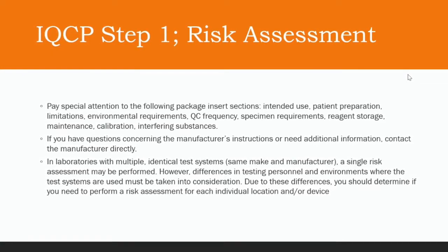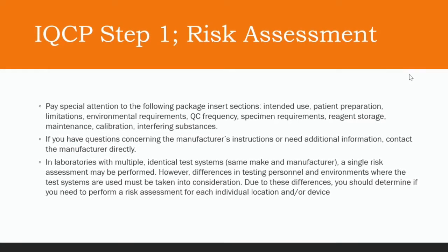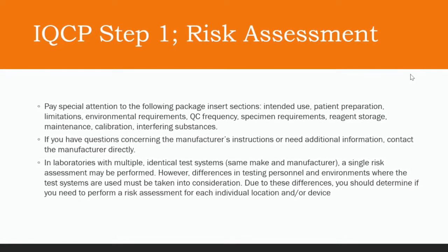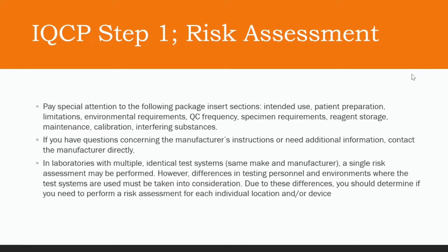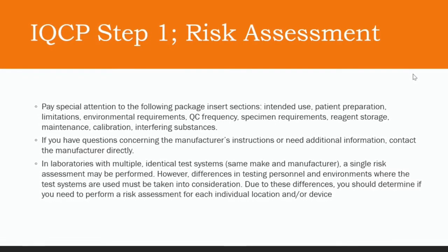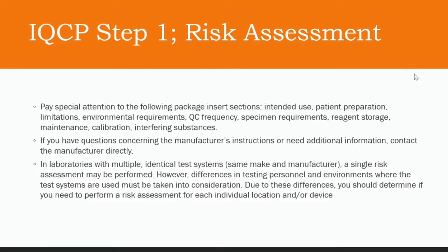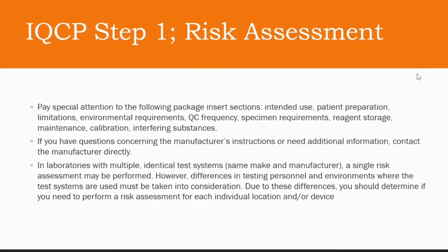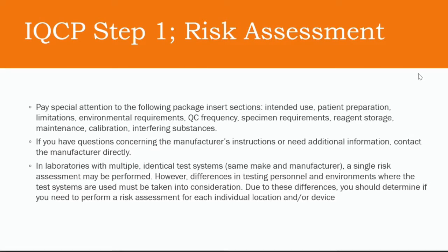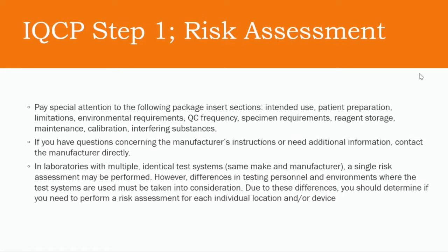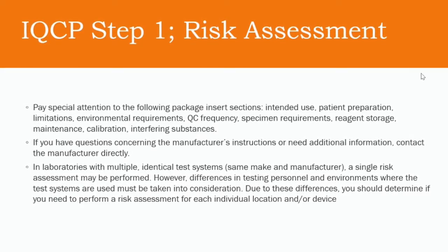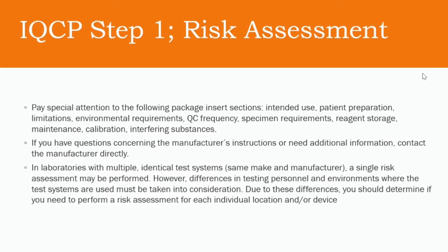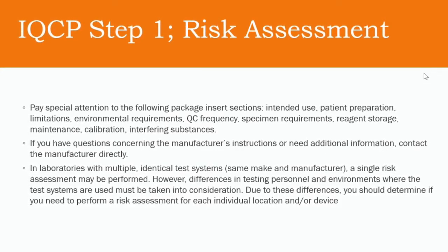Pay special attention to the following package insert sections: intended use, patient preparation, limitations, environmental requirements, QC frequency, specimen requirements, reagent storage, maintenance, calibration, and interfering substances. If you have questions concerning the manufacturer's instructions or need additional information, contact the manufacturer directly and keep the communication record. In laboratories with multiple, identical test systems, a single risk assessment may be performed.